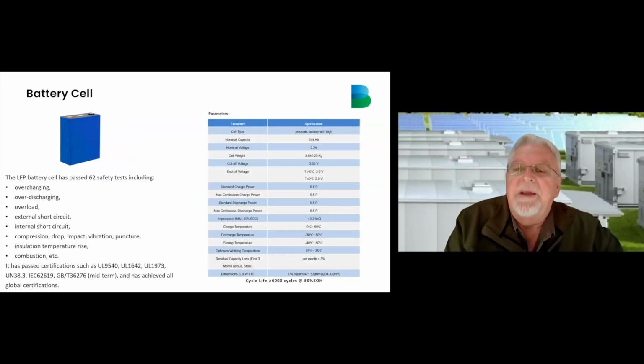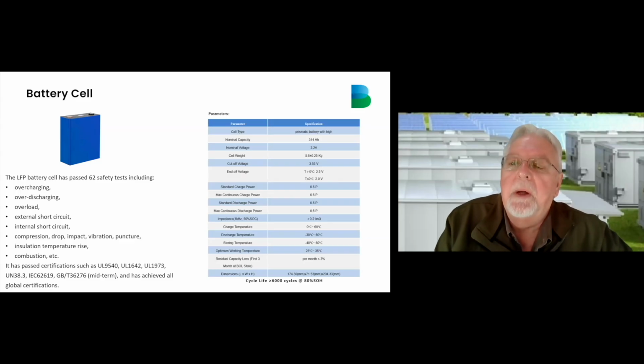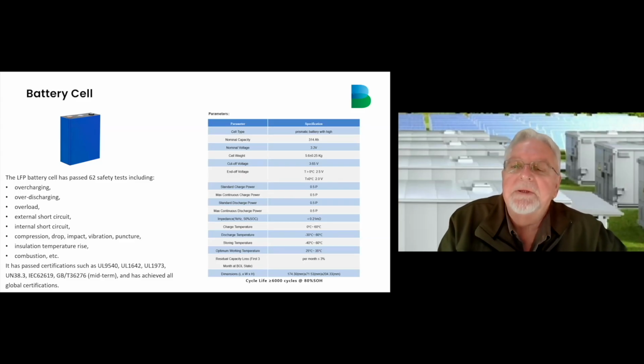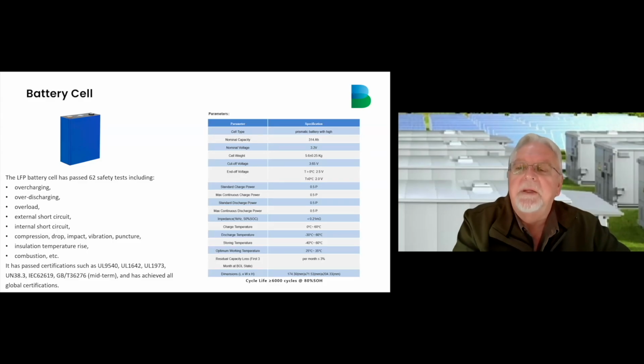Here is an example of a 314 amp hour 0.5C prismatic lithium iron phosphate cell. This cell is tested by the manufacturers to pass around 62 safety tests in order to get all the international IEC, UL, and UN certifications. This 314 amp hour cell has a typical cycle life of more than 6,000 cycles at the 80% state of health.